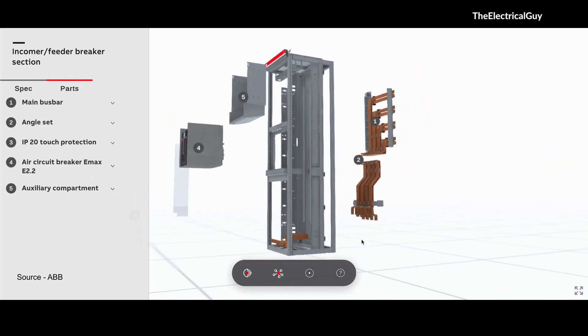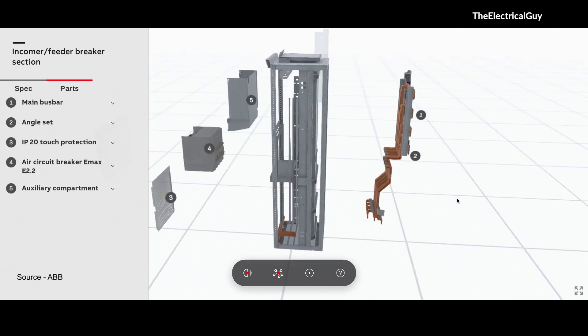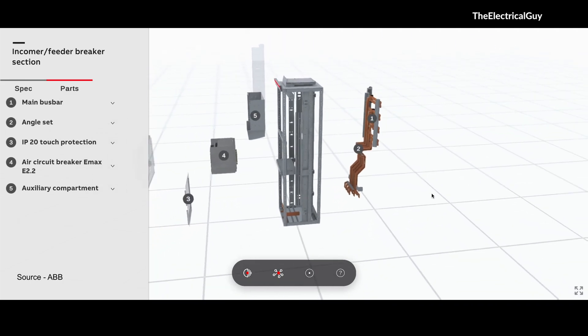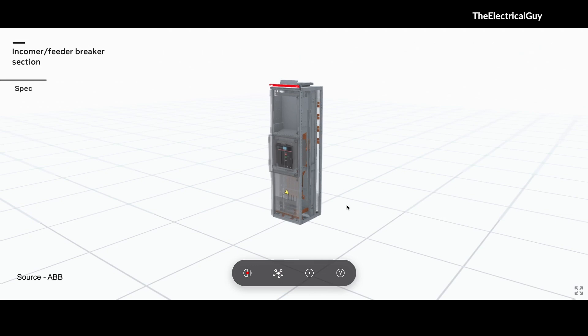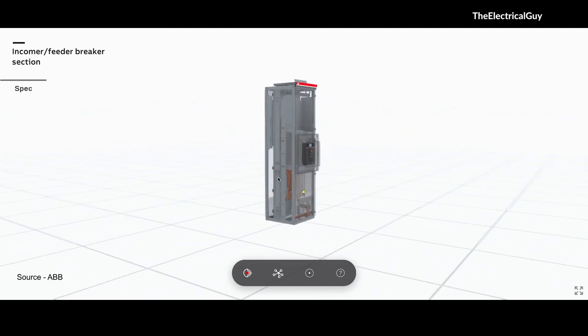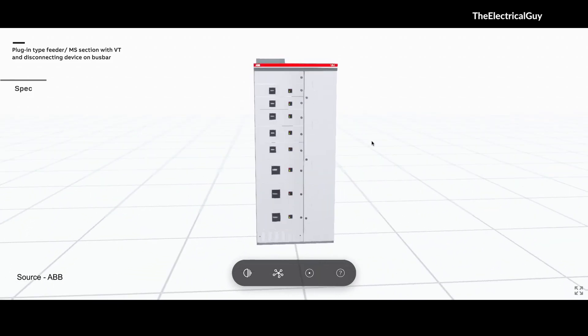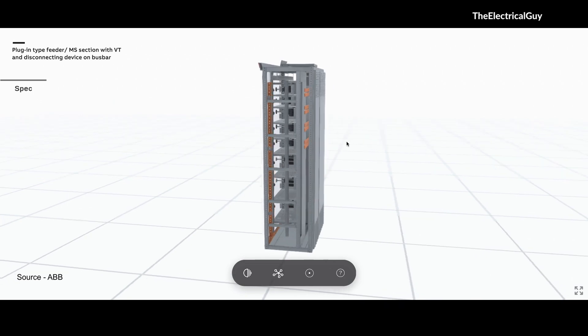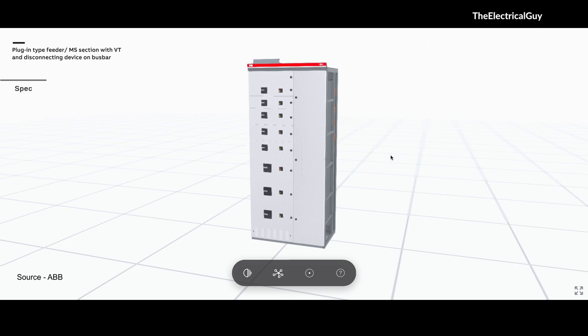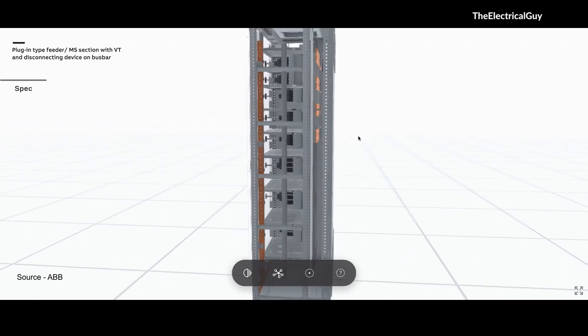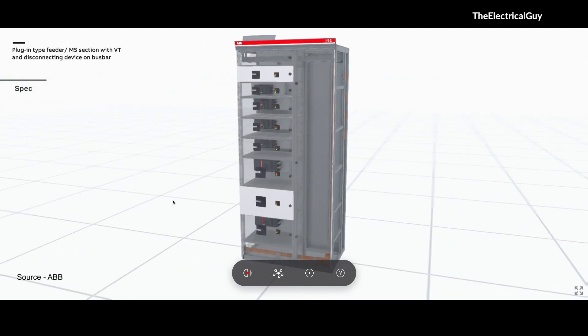This is the frame of the low voltage switchgear, which is very crucial. In low voltage switchgear, the most crucial aspect is the bus bar and the heating management — that is very important. This is a simple circuit breaker section panel, incomer or feeder. Now let us look at another panel. This is also a simple feeder panel, but it comes with withdrawable type MCCBs which you can remove as and when needed. This is a rear bus bar arrangement panel — you can see the bus bars running from the rear side.